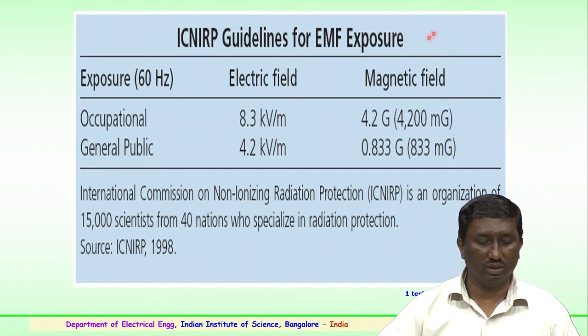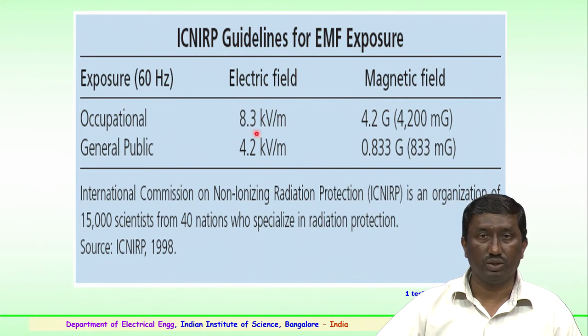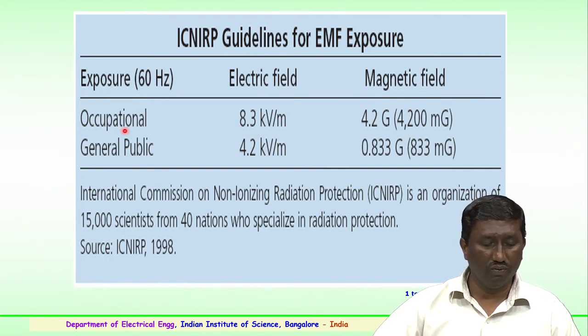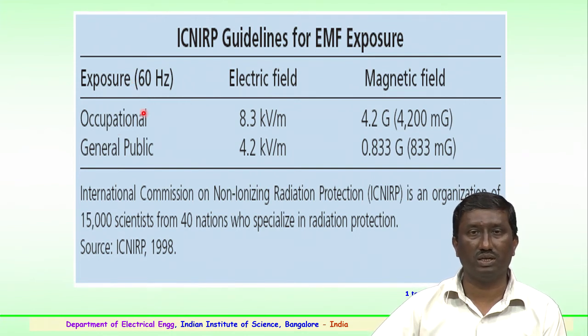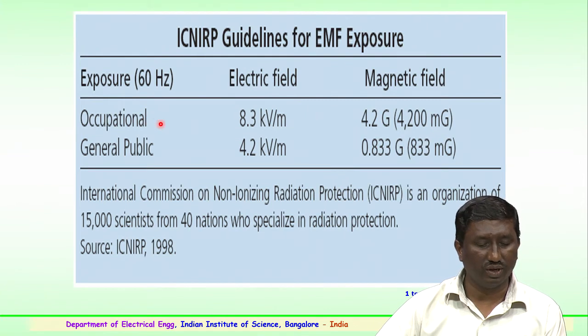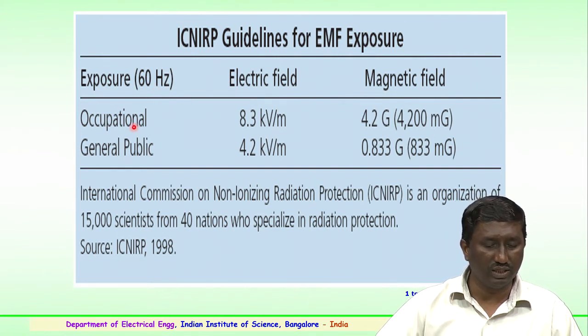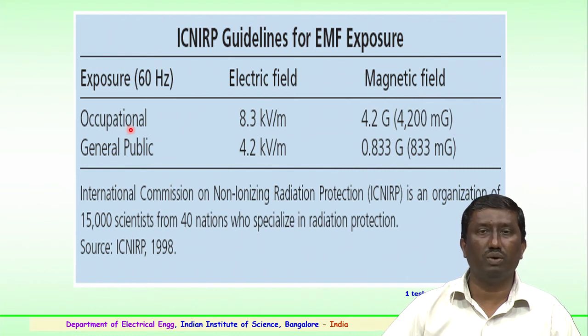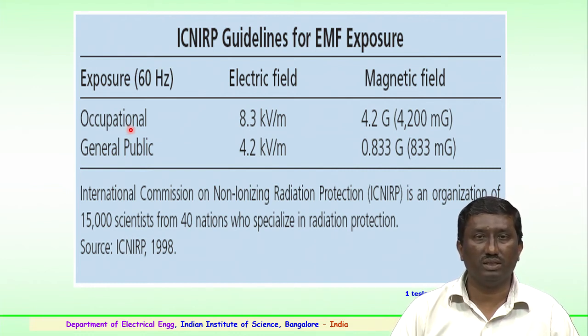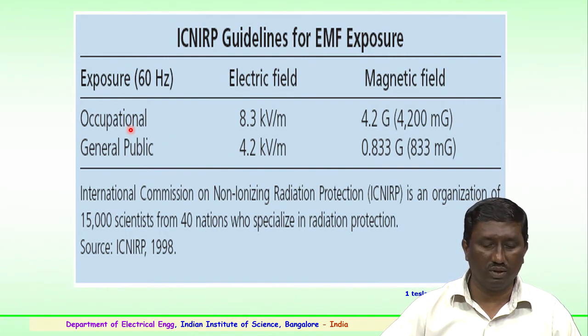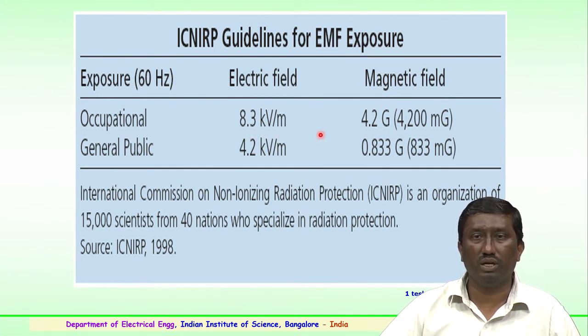Here are some of the guidelines framed by ICNIRP. You can see the exposure limits for 60 hertz power frequency supply, 60 or 50 hertz. In our country it is 50 hertz, while in some countries they follow a 60 hertz supply. The guidelines mention that for occupational exposure, people who are working in the utilities, say in substations, or who are exposed to transmission or substation electric and magnetic fields, should not be exposed to more than 8.3 kV per meter in the case of the electric field.